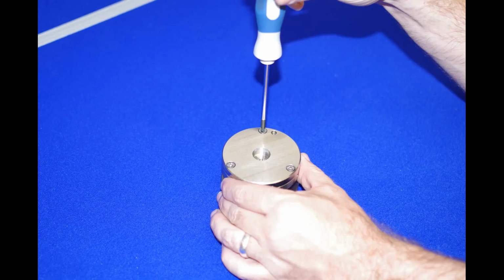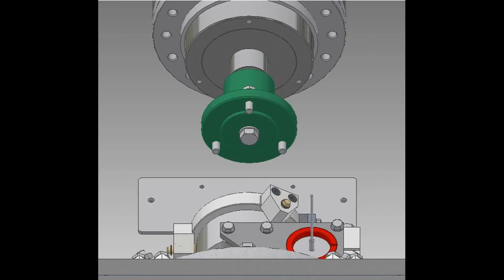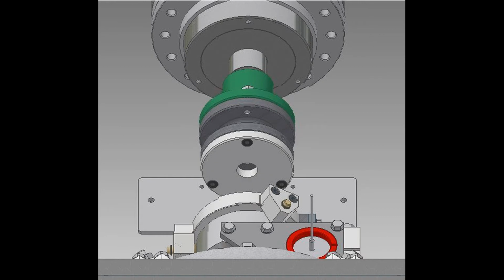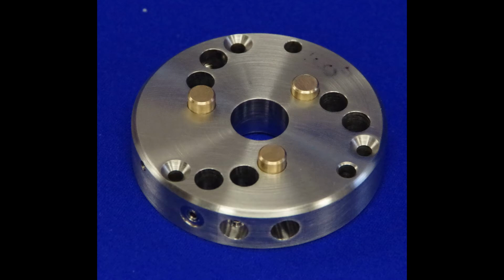Start by fitting a disc specimen to the upper specimen hub with 3 countersunk screws. Next, attach the upper specimen hub to the spindle flange with the 3 bolts. Pin specimens are fitted in a mounting plate and held in place with grub screws. These hold the pins in place during handling and are not intended to take the applied load, so the pins must be long enough to go to the bottom of the holes.